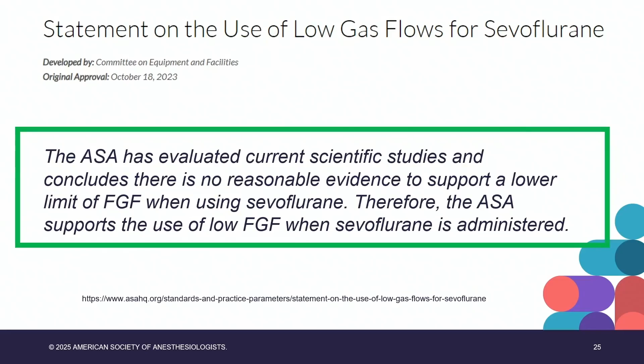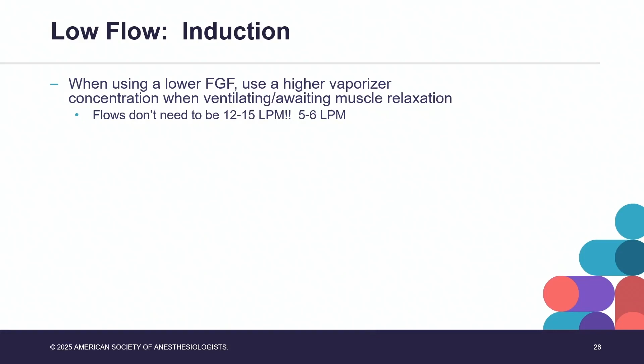So let's talk about the phases of anesthesia. So induction. When using a lower fresh gas flow, you will have to use a higher vaporizer concentration when ventilating or awaiting muscle relaxation. Flows don't need to be 12 to 15 liters, and I am guilty of doing that for a number of years, but I have changed. So, 5 to 6 liters, assuming you have a good mask, is appropriate.